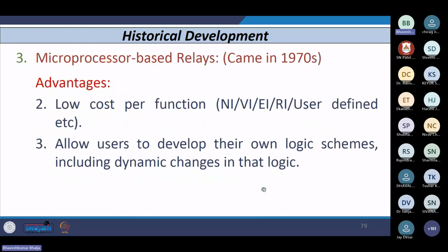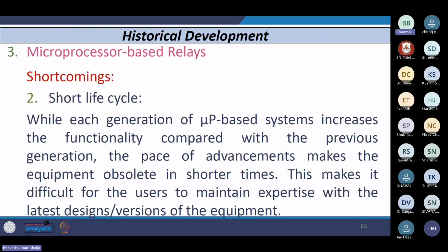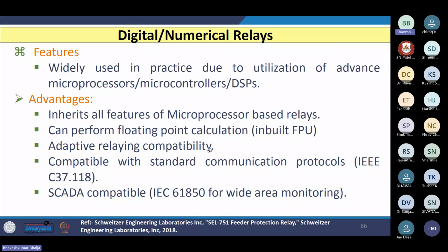Okay, now I am hurriedly going through the different types of relays you have. If you look at the latest generation of relays, I thought you must be aware of this, these are digital or numerical relays, right? They are usually compatible with communication also. They are compatible with IEEE C37.118 and IEC 61850, which are substation automation protocols, and they usually use DSP controllers, right?